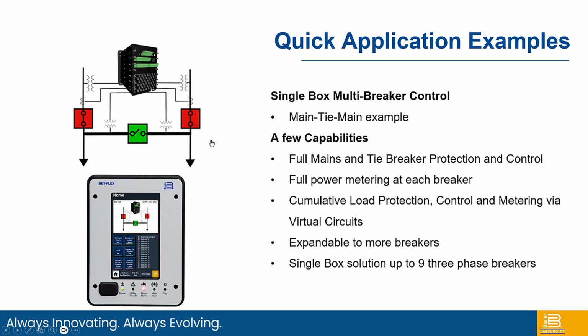In addition to just the breaker control, we can also do full protection, such as intertie protection with this exact piece of hardware. We can also do cumulative load. So maybe the plant or the facility down here wants to know how much power am I receiving from this source plus this source for whatever reason. The Flex has what's called virtual circuits that can accumulate and sum those 2 things and look at it as if it's a real measurement from a single current transformer and voltage transformer.